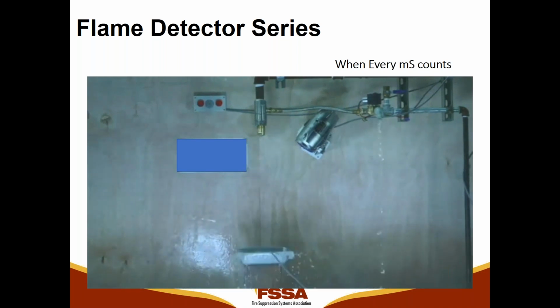So about 5 to 9 milliseconds with UVIR, about 20 to 30 milliseconds with the IR3. So very fast detection. You'll see the light comes on when the detection occurs. Connected to a water supply solenoid, and there's your high-speed deluge system activation.